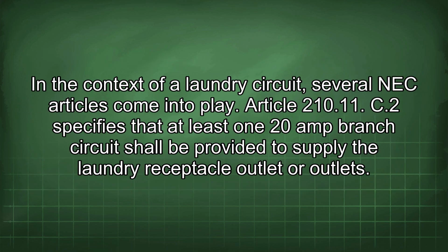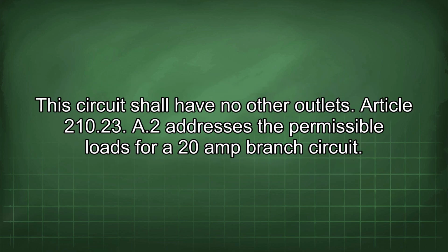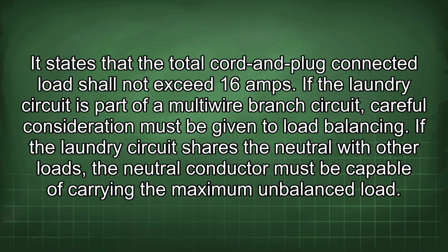In the context of a laundry circuit, several NEC articles come into play. Article 210.11(C)(2) specifies that at least one 20-amp branch circuit shall be provided to supply the laundry receptacle outlet or outlets. This circuit shall have no other outlets. Article 210.23(A)(2) addresses the permissible loads for a 20-amp branch circuit. It states that the total cord and plug connected load shall not exceed 16 amps.